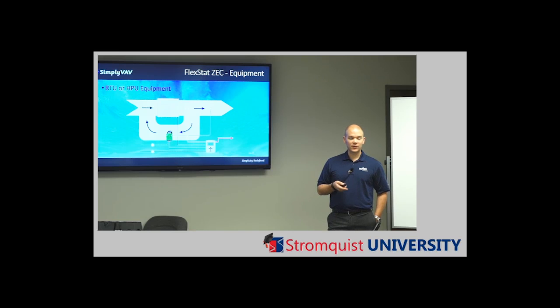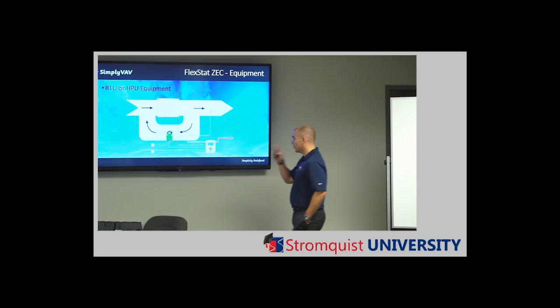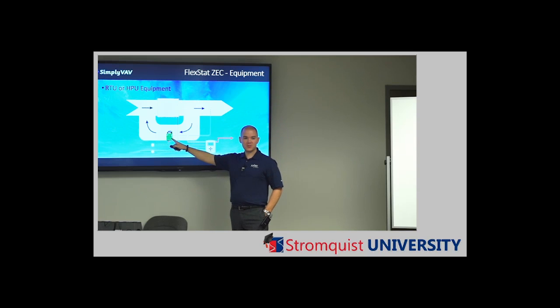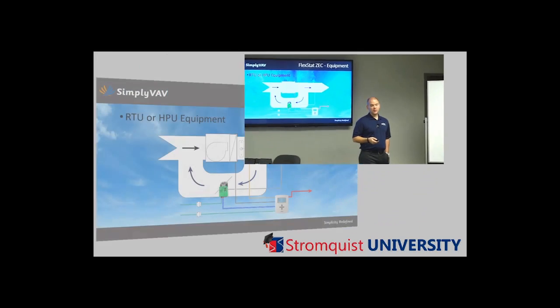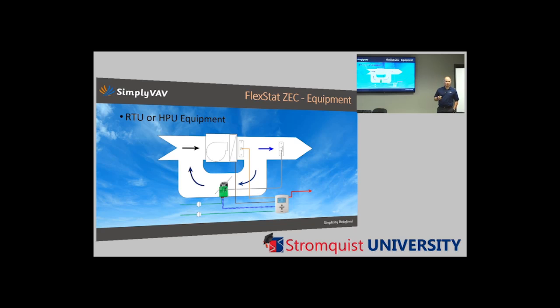So the last thing I'll call attention to is we have a static pressure bypass controller for these rooftops as well. It's actually our analog VAV, our new small footprint analog VAV controller. But if you run it in reverse acting mode, now we're controlling static pressure. So you can apply this to the bypass damper. There's a potentiometer to set what that static pressure limit is. So 1/2 inch, 1 inch, whatever you'd like, up to 2. And then you just let it go. You can either set it with the pot and have it be standalone, or the FlexStat can give it its static pressure set point.